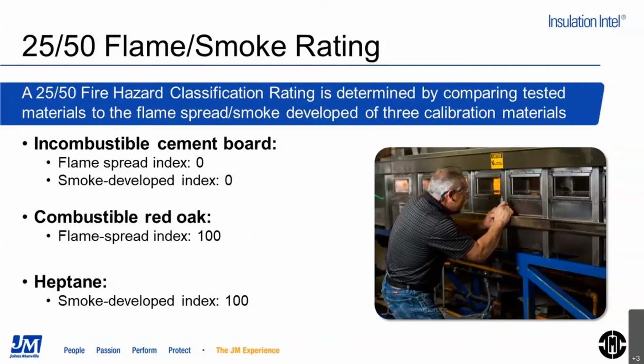For the other extreme on the flame spread, we have combustible red oak. It is combustible, and that is given the index of 100. When we are calibrating with red oak, we want to see the flame spread the length of the tunnel very fast. Within 5.5 minutes plus or minus 15 seconds, the flame needs to travel all the way through. That's our extreme of combustible material, just to give you an idea of what we're talking about. And for the smoke, we use heptane. In previous revisions of ASTM E84, red oak was used, but in the most recent, it was switched to heptane because it's more reproducible. As you can imagine, red oak is a natural material, so there could be some variability from it. And so now we're using heptane.